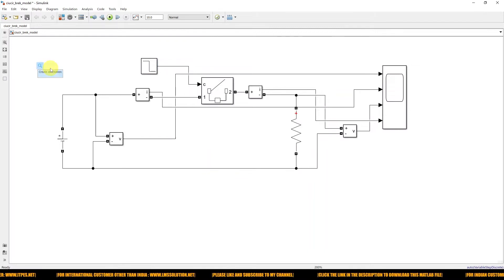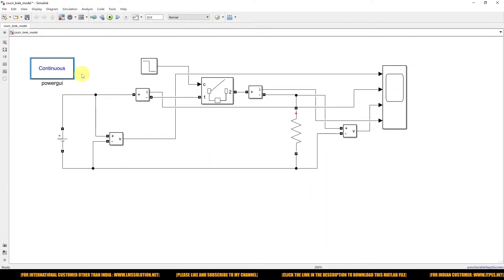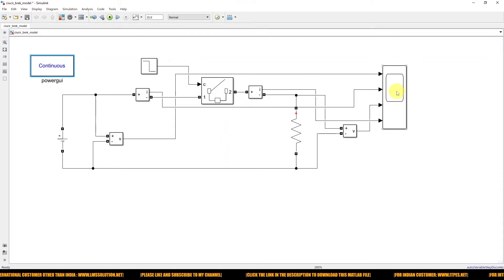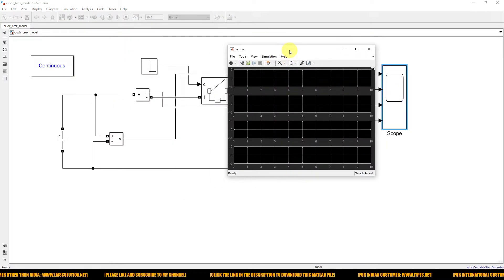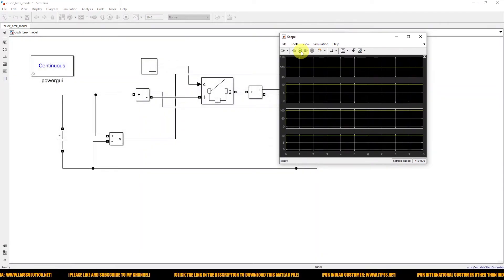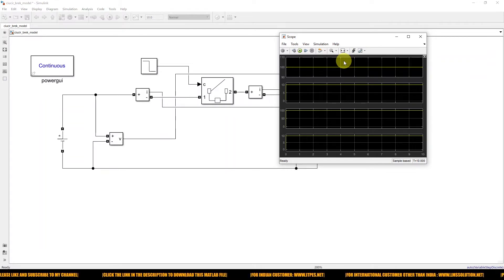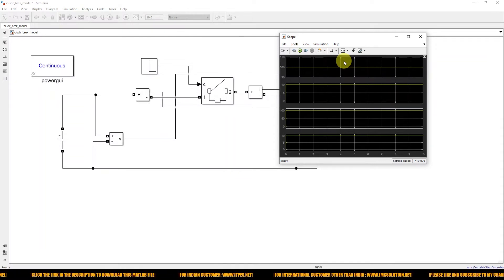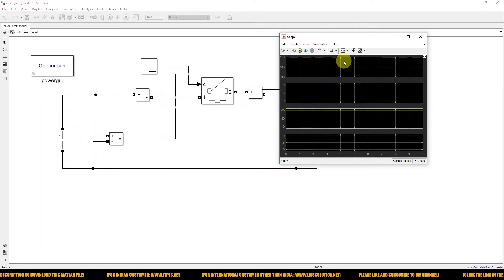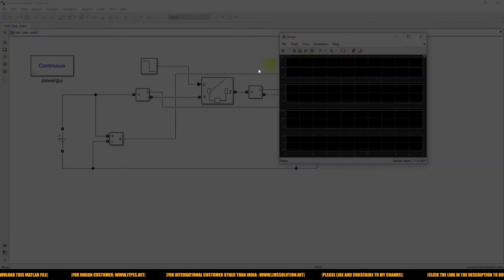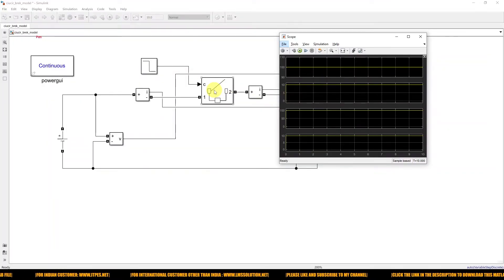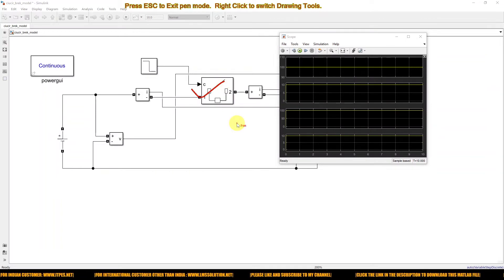Now I'm going to use PowerGUI because we are using power system blocks. Running the simulation, you can see that even though the opening command is given to the circuit breaker, the circuit breaker is not opening, because we have a continuous current flow in the load. So this is the problem — you cannot use this single-phase AC circuit breaker for a DC circuit. Therefore, we need to go for a DC circuit breaker.